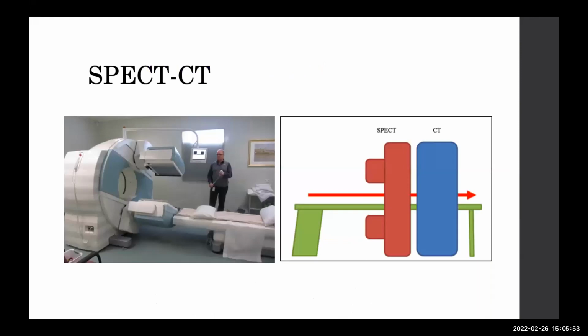Now we come to another technology, which is called hybrid technology, SPECT-CT. If you see in this image, this is a conventional gamma camera gantry. And these are the two detectors, the anterior detector and the posterior detector. And the posterior part of this system has a dedicated CT scan. You can see this pictogram here. This is a CT scan. And this is the gantry of a gamma camera, which is placed in tandem on a single platform. And this is the bed, which moves within the gantry.